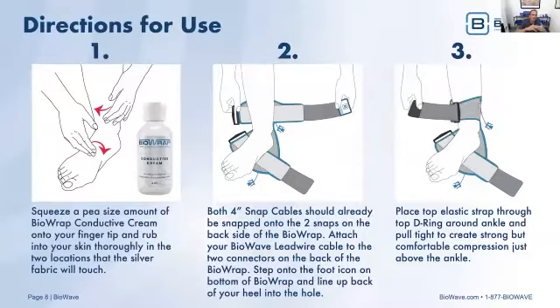It's okay if the cream spreads beyond the region where the silver fabric touches, as long as we're getting the entire top, around, bottom of the foot, and all the way around just above the ankle area. So you want to rub it in. You don't want a huge amount of white cream staying at the surface. That's very important because that's going to enable this device to work properly. Both 4-inch snap cables that I pointed out before will already be snapped into the snaps, one on the upper electrode, one on the lower electrode. So just confirm that they're already there and attached.